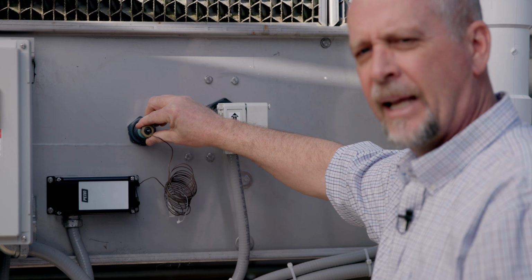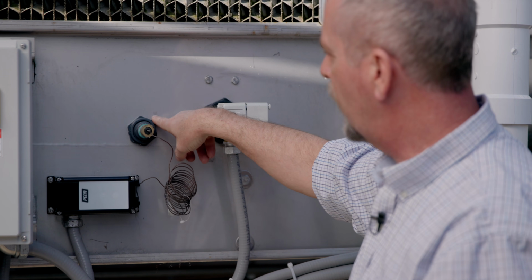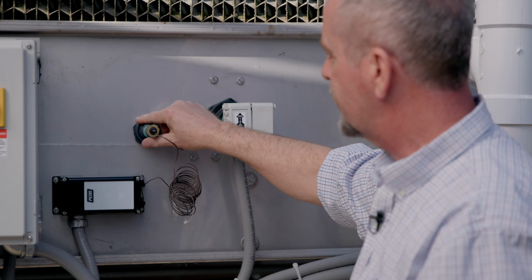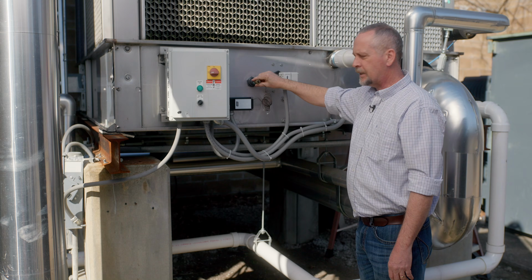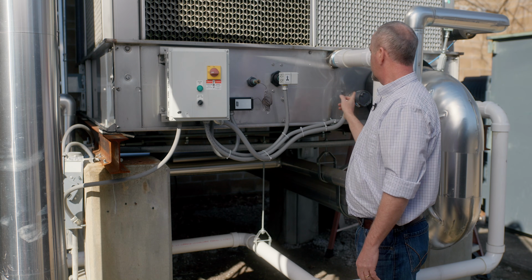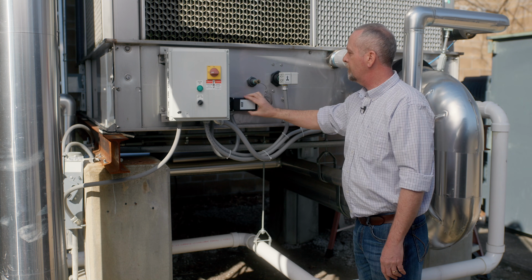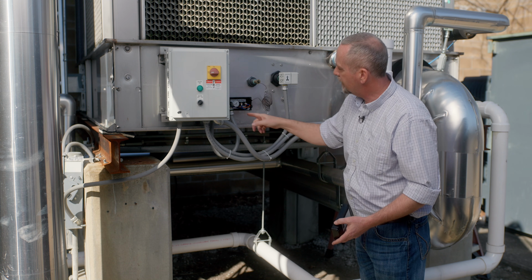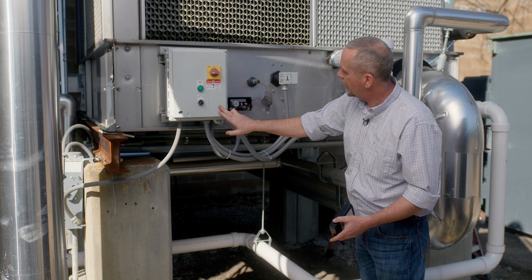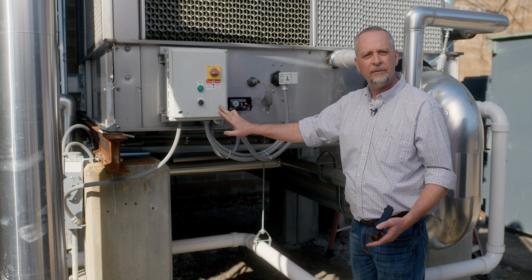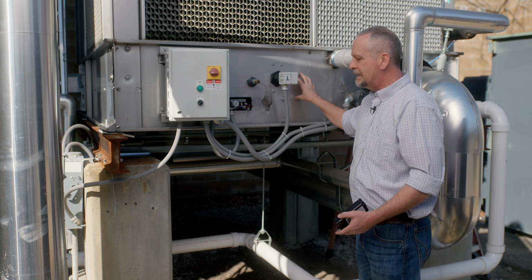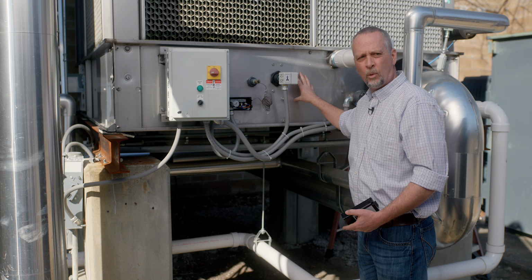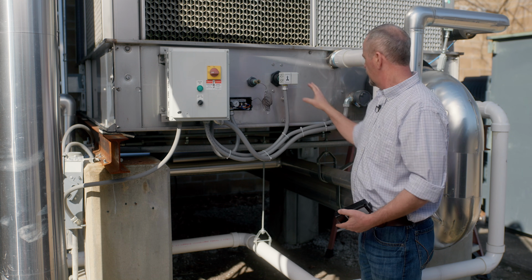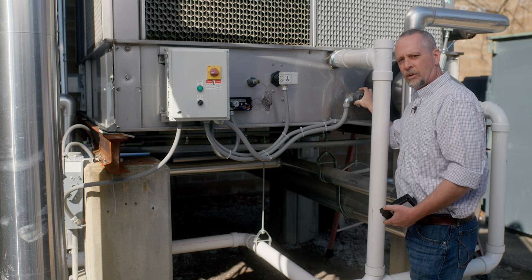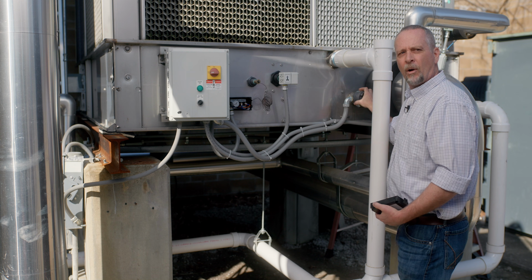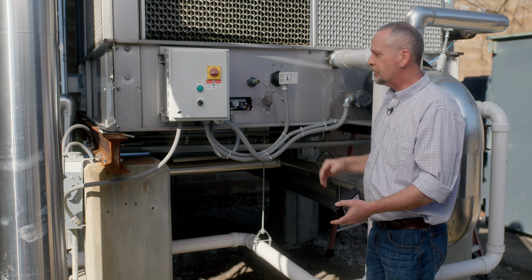Here's my thermostat that is in a basin well inside this cold water sump, and that's looking at my temperature. This is what's controlling my heater to come on and off. Right now, I don't know if you can catch that in the camera, that dial's set to about 45 degrees. So if the water inside of this sump gets below 45 degrees, it will energize this high voltage basin heater to heat that water back up to 45, and then it'll shut off.